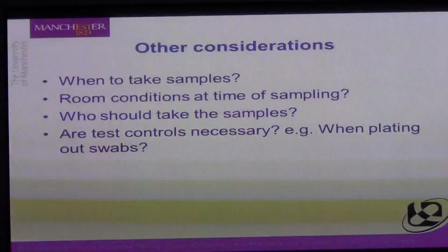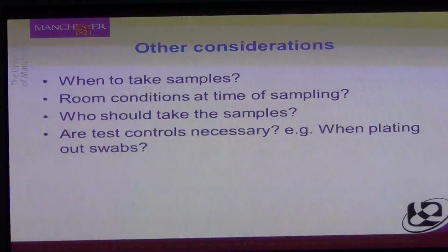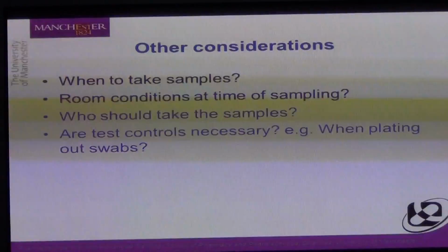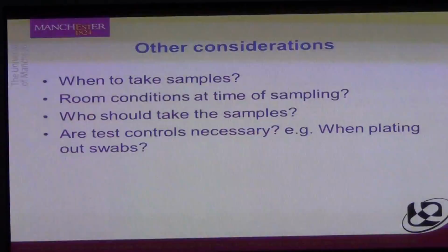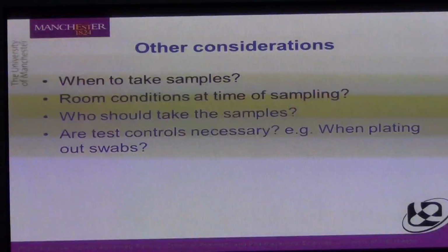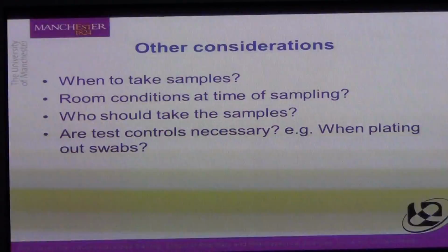Other considerations which will inform your plan is when to take samples, how the room should be when you sample. So if there's normally people in the room, you should really sample when there are people in the room. Or if there's a certain item of equipment normally running, then you should really monitor when the item of equipment is running.